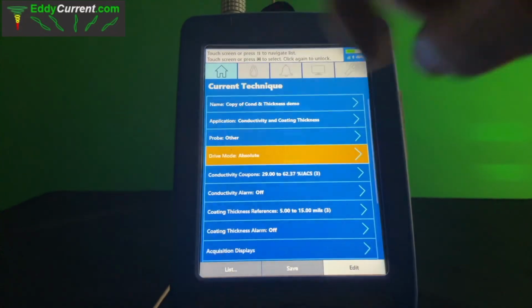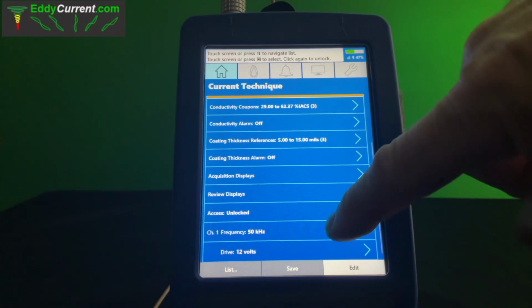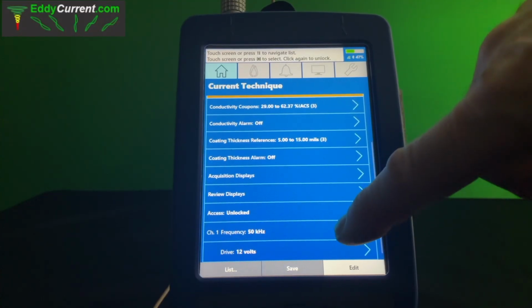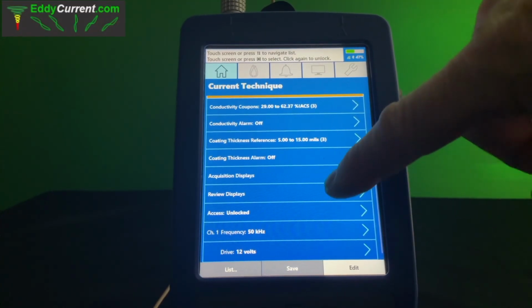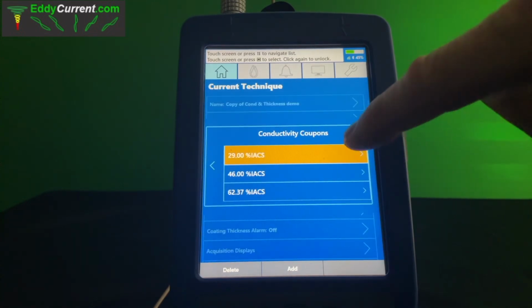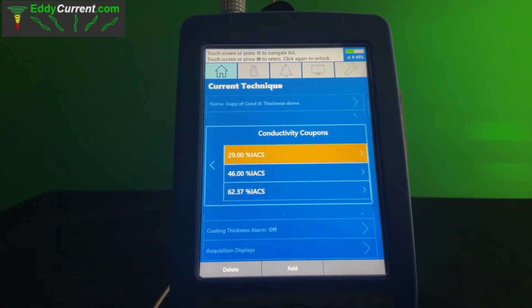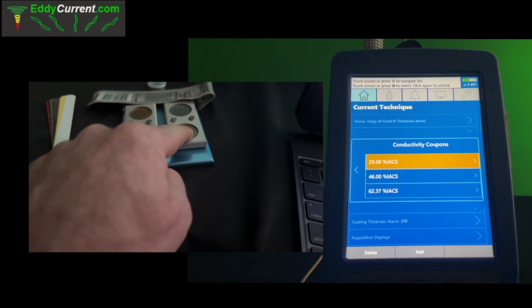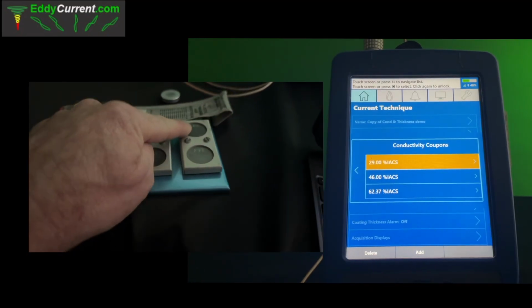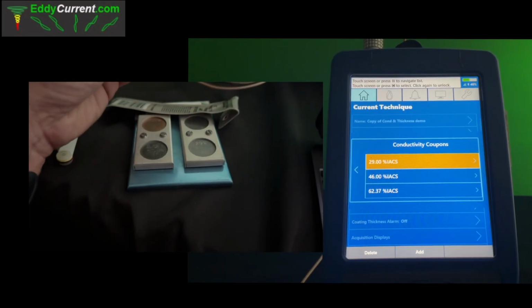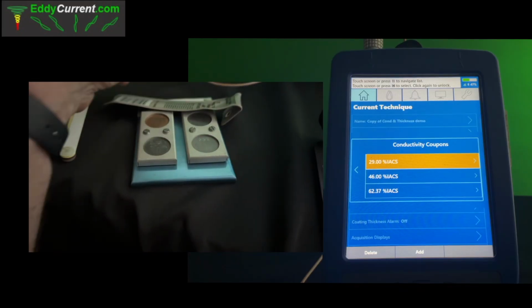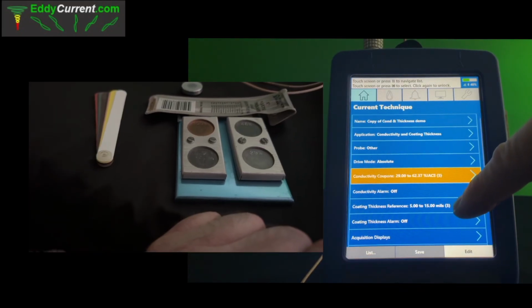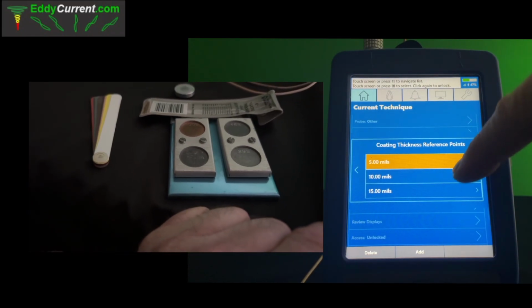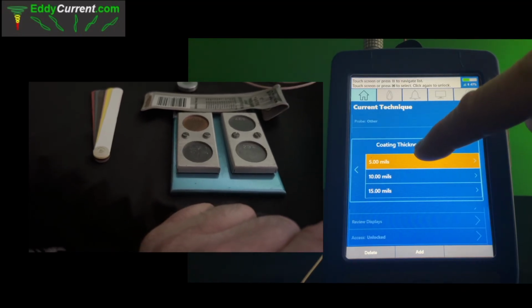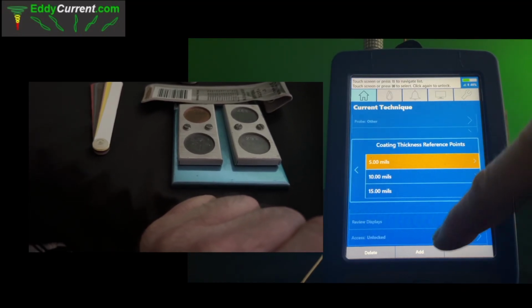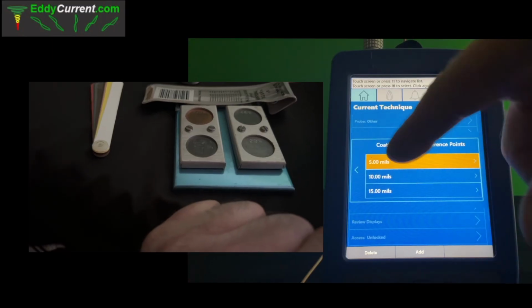It's an absolute probe. It's 50 kilohertz, which is not what I would normally use, but it's the only probe that I have here that's fairly stable. And the conductivity coupons that I have here are 29, 46, and this one is 62.37. Liftoff thickness shims, I'm going to be using 3 of them. One of them is 5 mils, 10 mils, and 15 mils, so you can add other values if you have them.